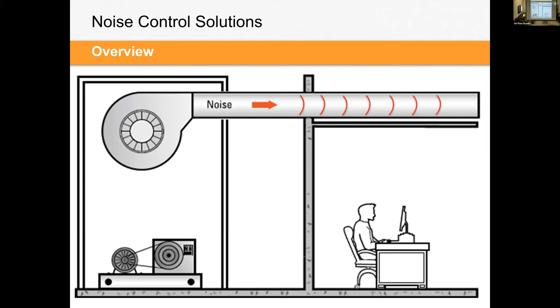That sound energy is going to be transmitted easily through that duct into maybe the occupied space at the end. Another path for noise that's often forgotten about is the breakout radiated noise from the duct itself. And this can cause a lot of problems and issues. This is obviously fabric duct here and may not have the same concerns, and this is distributing air in the space. But if you had a fan in a mechanical room on the other side of the wall, and this was a thin gauge duct, that sound energy could cause a lot of problems in the space because it would otherwise be radiating into your environment.